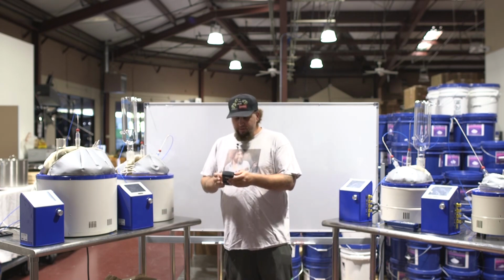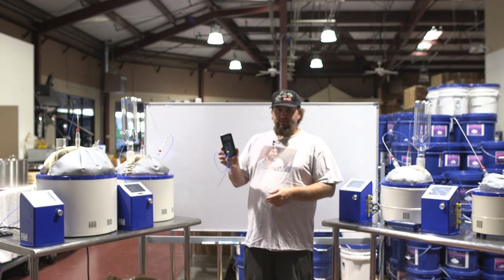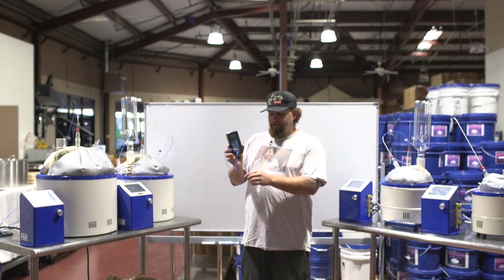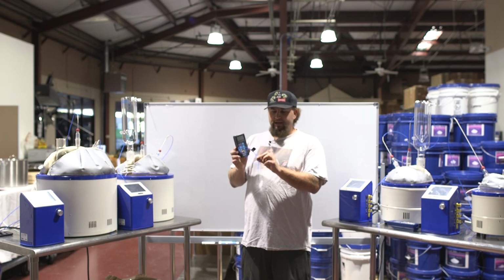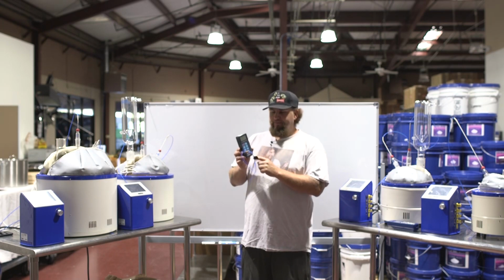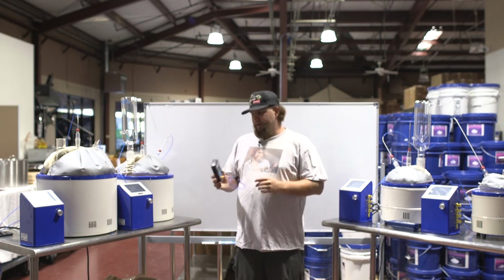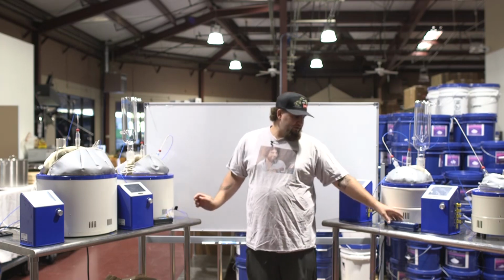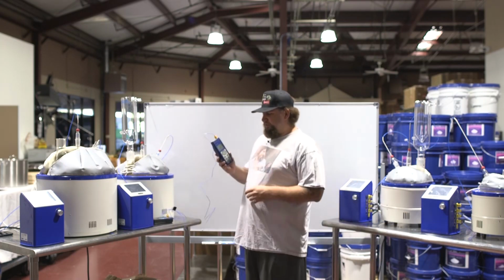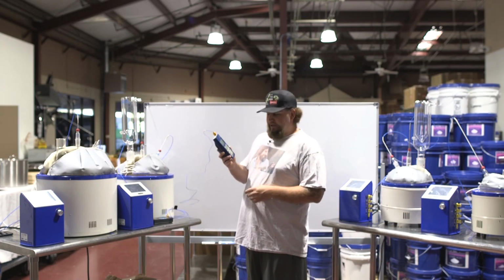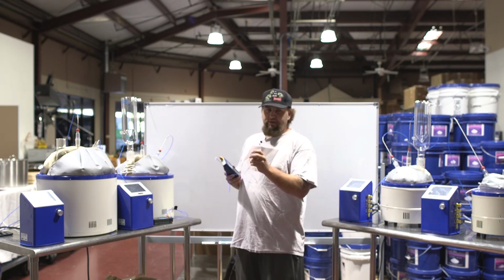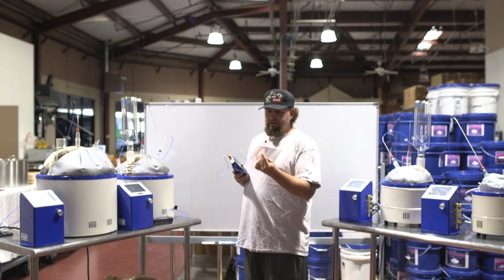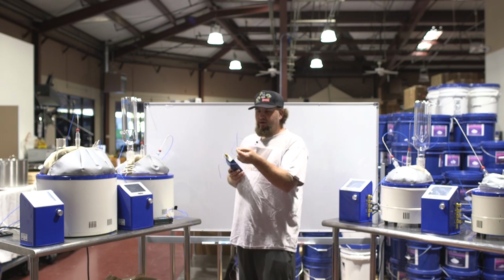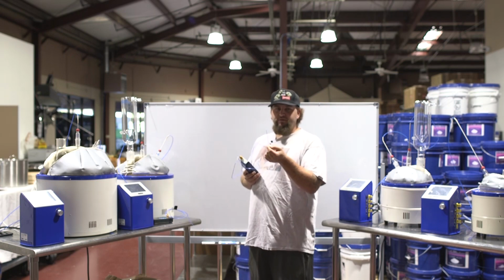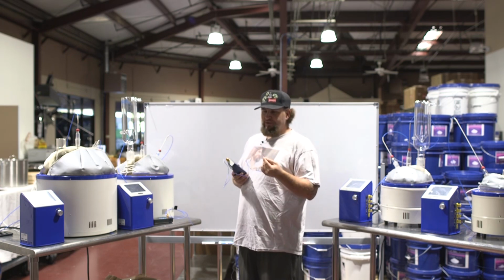So we use a traceable brand thermometer. I actually have a particular unit that I hook up to this and I can calibrate. These are pretty close, but not all that close. What we do here is we purchased a Reed, fully certified with a certificate thermometer with a certified probe. Now, as you can see, these probes are just like little wires. They aren't very robust, but they're very accurate for immediate temperature results.